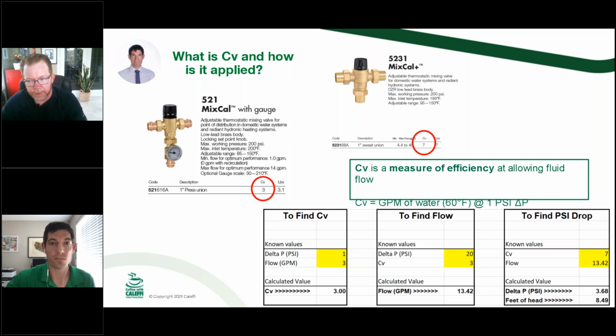If you've ever been inadvertently burned by a CV number, which I know I certainly got very close to being burned by a CV number with a Caleffi product, where I made a selection. Unfortunately, we did actually check it and go, ooh, Cody and I on the team were looking at that going, this is the wrong valve. So you always want to pay attention to that. It's important that you keep an eye on it for sure. So yeah.